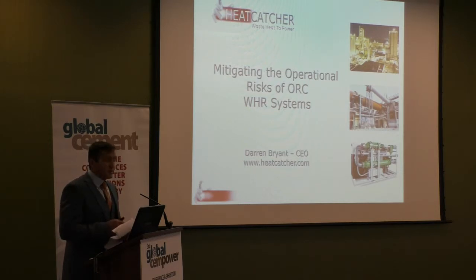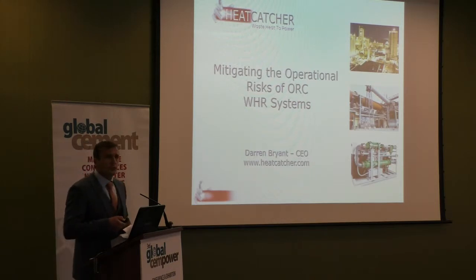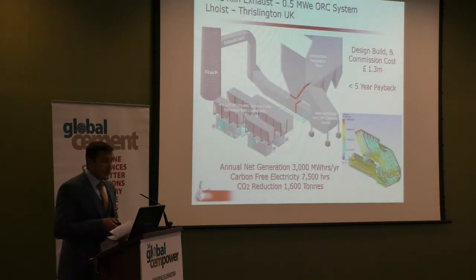And the clever part about this technology is the integrated power module. So it's got a small micro turbine inside, and on the right hand corner there's a small micro turbine there. It's an integrated power module. So within that you've got the alternator as well, and the power electronics feeding it. So it's a sealed unit. So from a refrigerant point of view, you've got less risk of leak, and the run hours on that are 100,000 hours. So you've got a lot of reliability for a long time. And back to there. So we're inside the containers.